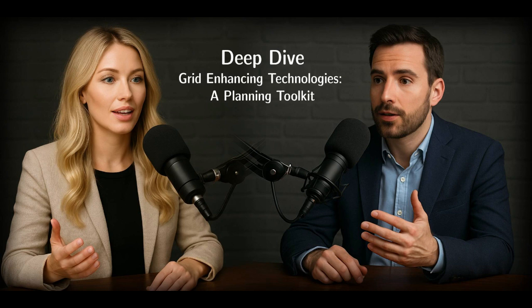And then kind of the ultimate FACTS device is the Unified Power Flow Controller, or UPFC. UPFC sounds comprehensive. It is highly advanced. It offers simultaneous control of both real and reactive power flow, independent voltage regulation, phase angle control. It basically combines all the capabilities into one device. Wow. Precision? Sub-cycle response, and typically plus or minus 1% power flow control precision. Very fine control. What's the economic case for something that advanced? Well, if a UPFC can provide, say, a 300 megawatt capacity increase on a constrained path, the annual value from capacity, congestion reduction, stability benefits, it could easily be over $16 million a year.